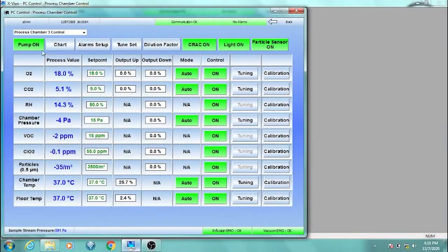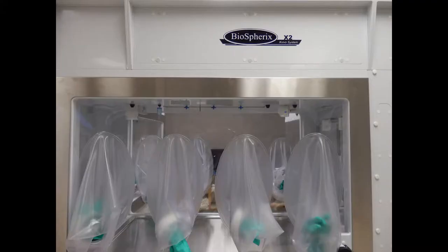Once you have received your replacement sensor pod, turn control off in the module where the sensor pod is being replaced. Locate the enclosure panel the sensor pod is located behind, usually above the module where you are changing the pod.